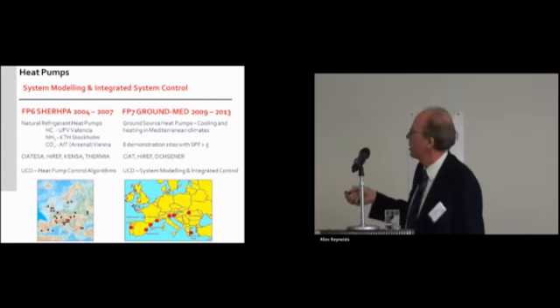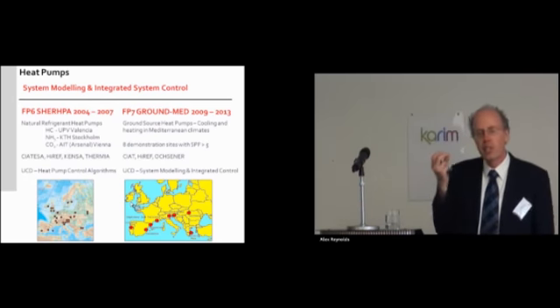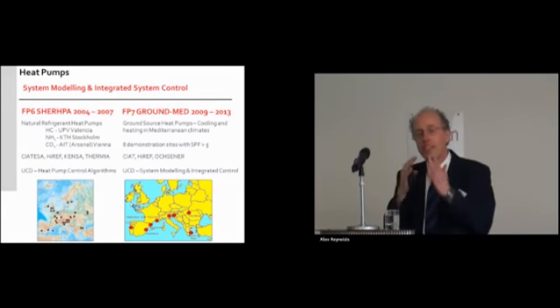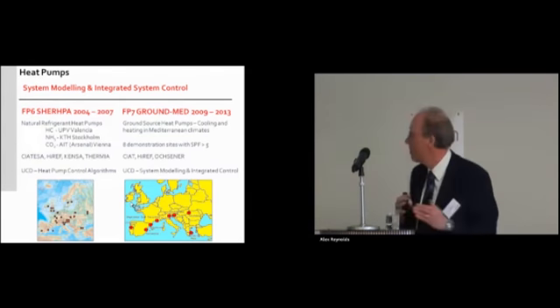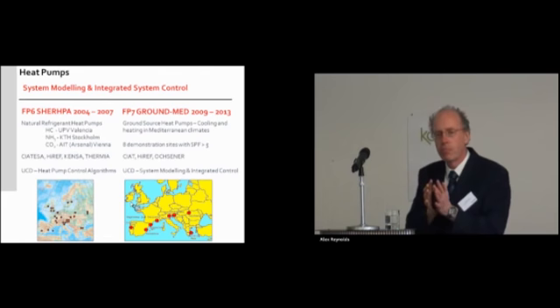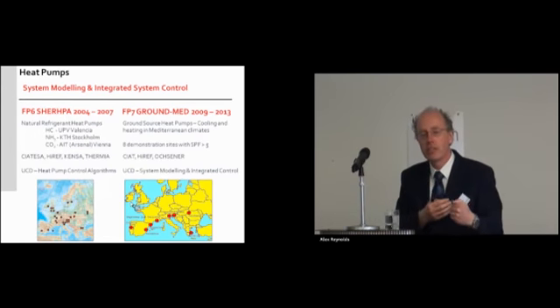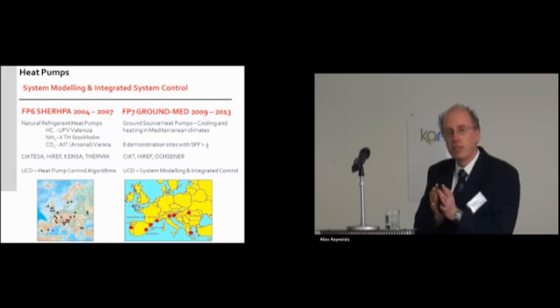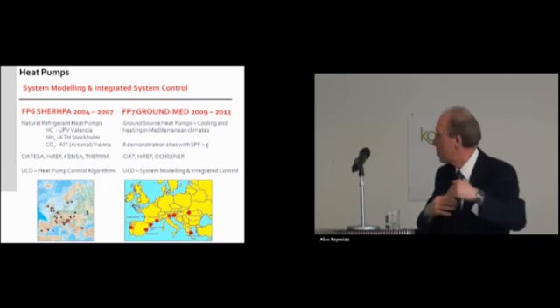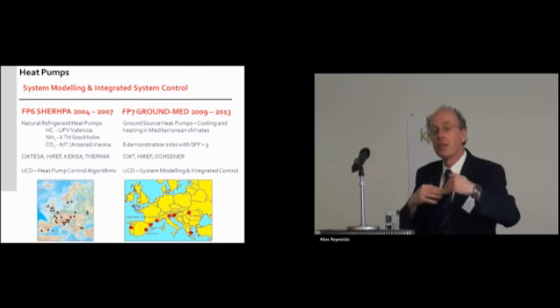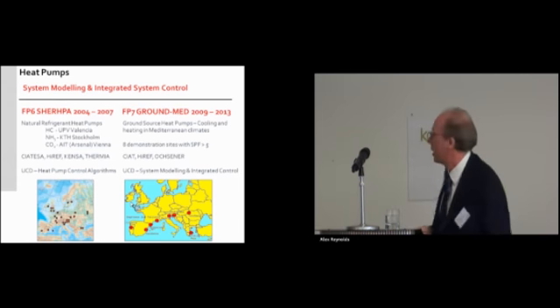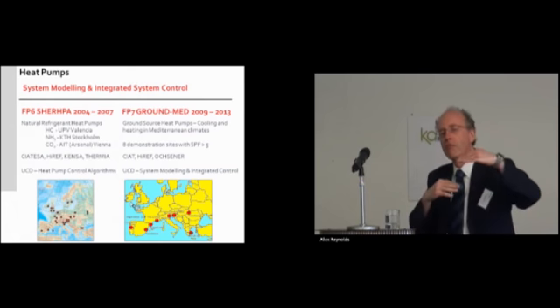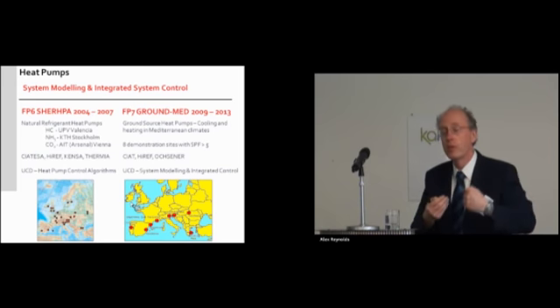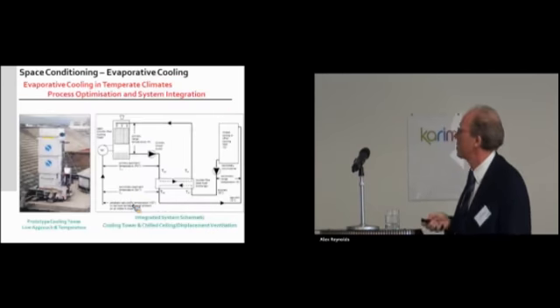And you'll see one point here, the system should have what we call a seasonal performance factor. This is, rather than the COP, which is looking at the steady state performance of the system, seasonal performance is looking at the integrated COP, including some of the parasitic consumption, such as the pumps and fans associated with the system over an entire season. And the target is to design very effective systems and to operate them through the control algorithms effectively so that their seasonal performance factor is greater than 5 in this case, which really means you have to design for very low temperature heating, high temperature cooling, and also to have very well designed components and to have very good control within the system as well.